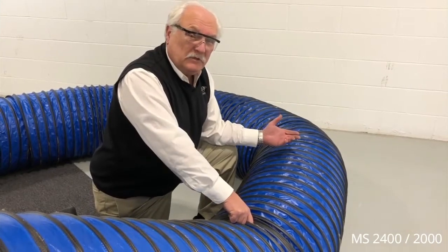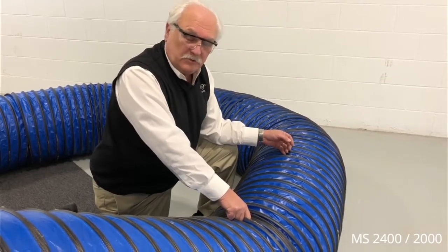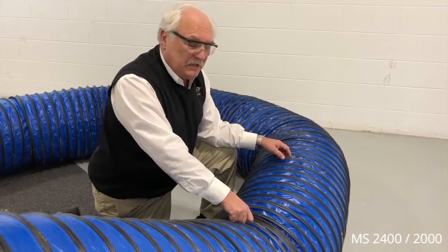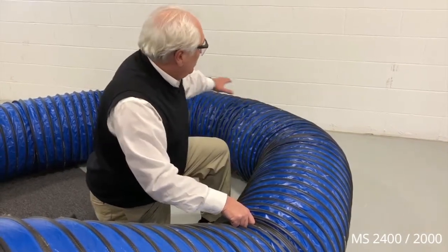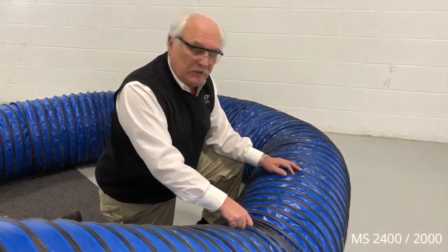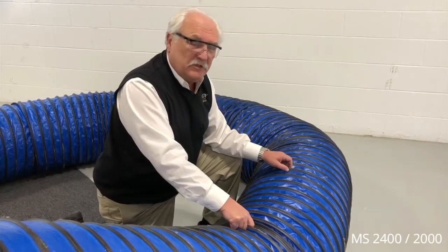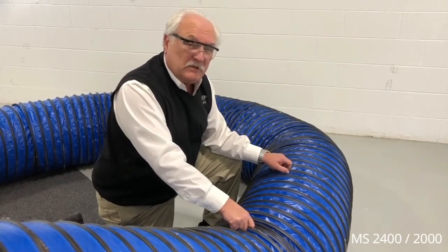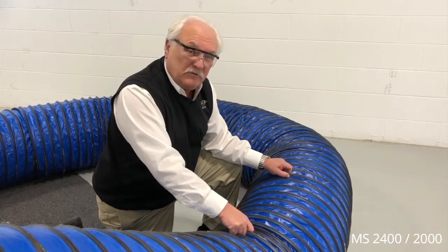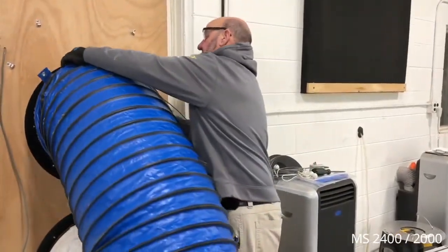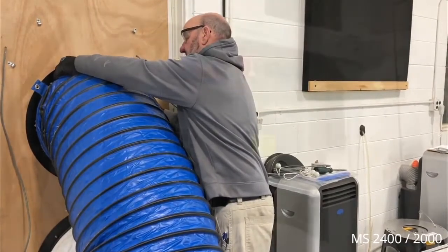The return ductwork is under a negative pressure or a suction pressure. Care should be taken to leave very large radius bends for the return airstream, and the bends should be secured so the unit doesn't suck the duct together and restrict airflow. Connect the other end of the ducting to the room that needs to be dehumidified.